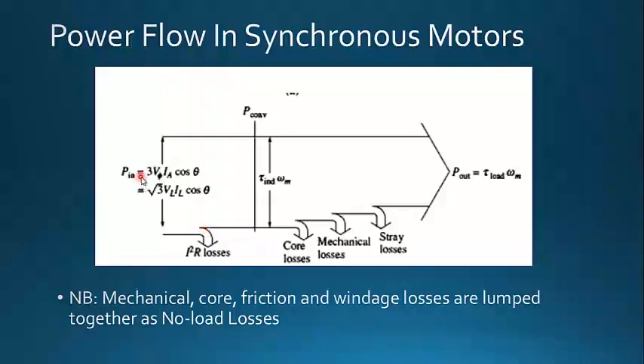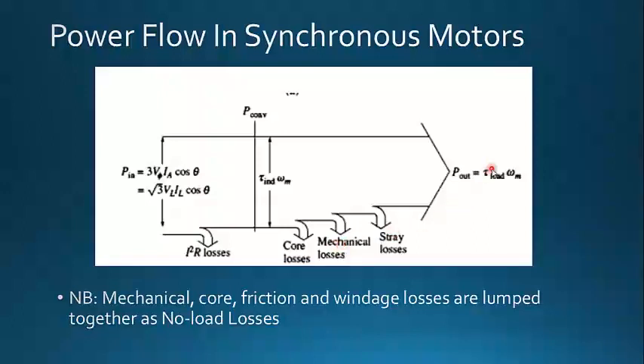So if we have our three-phase electrical power as the input, the power flows inside the windings. Having current flowing through the windings means we have I-squared-R losses in the form of heat. The remaining power then faces core losses as a result of eddy currents and hysteresis losses. We also have mechanical losses from friction and other sources. After all these losses, we get our mechanical power as the output, which equals load torque multiplied by the speed of the motor.